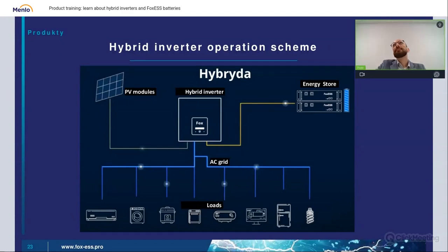And in this, let's for example say that this unit works on default with this self-use mode. Then, if you have PV modules powered, if you have your inverter powered up, and your battery is empty, this energy from PV modules will firstly provide power for the end customer's loads, and if there is excess power, this power will charge batteries. And if you have power from PV and your battery is full, you will provide energy for the end user and then export this excess volume to the grid to power your neighbor or else.